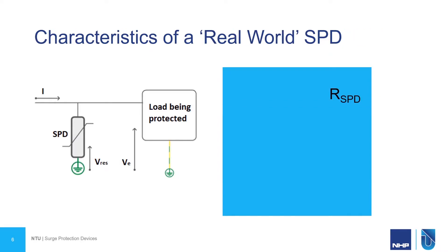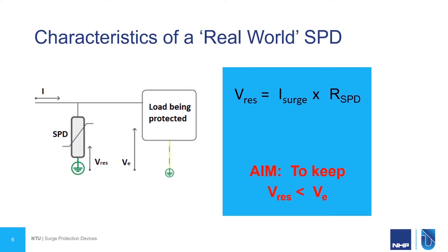However, unfortunately in the real world we have some limitations. Under high voltage conditions, the SPD will modify its impedance down to almost zero. However, there's no such thing as a perfect conductor, so there will be some resistance present. Combining that with surge current that's in the kiloamps, we'll be left with a residual voltage across the SPD. The aim of a surge protection device is to keep that residual voltage below the withstand of our protected load.